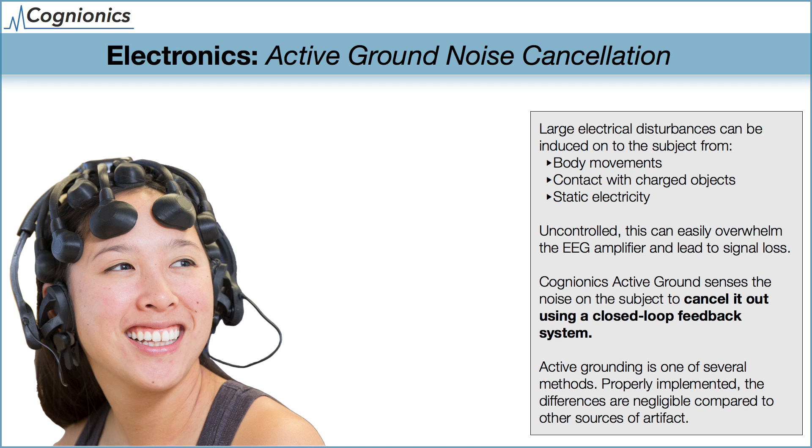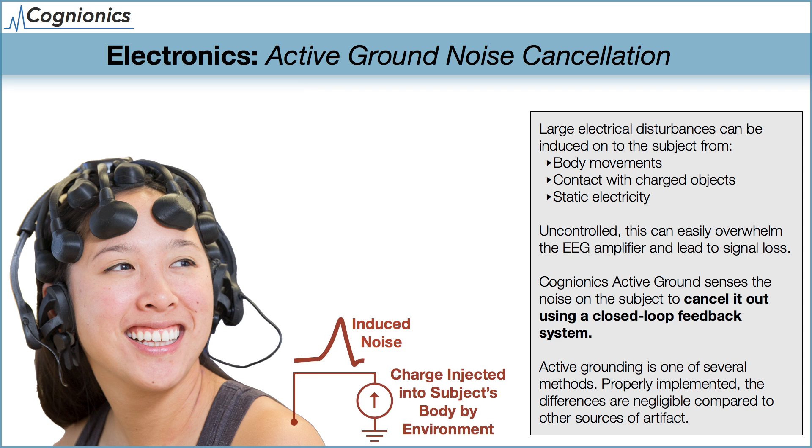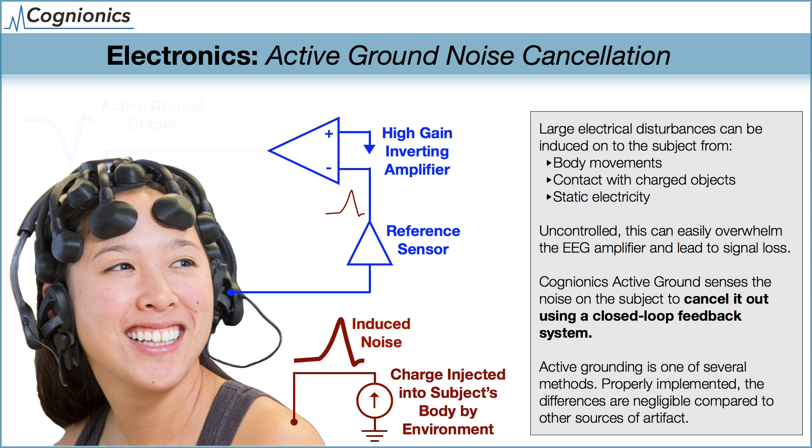In addition to shielding, our system also uses an active ground noise cancellation system. Electrical noise can be directly coupled into the subject's body and generate a common mode artifact that appears on all the channels. Common mode electrical potentials can be injected into the subject by body movements such as walking, and also by nearby people and objects — the magnitudes can easily be thousands or millions of times greater than that of the EEG. The Cognionics Active Ground System uses the reference electrode to sense the disturbance. A second amplifier inverts the signal and cancels it out using a closed-loop feedback system, eliminating the differential between the subject and the amplifier, which results in a clean EEG recording. Active grounding is one of several techniques used to minimize common mode disturbances and ensure that the potential of the amplifier tracks the subject's body.